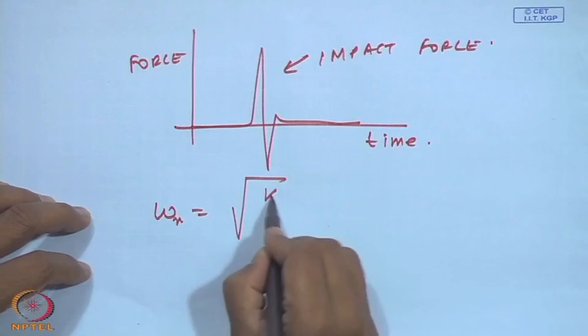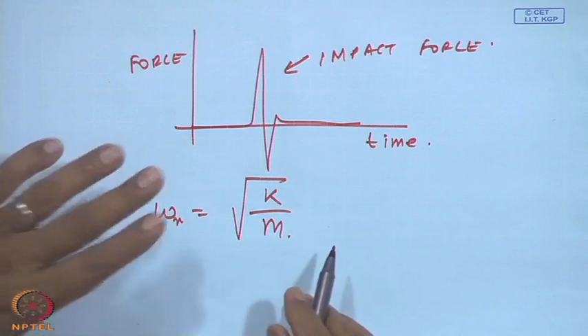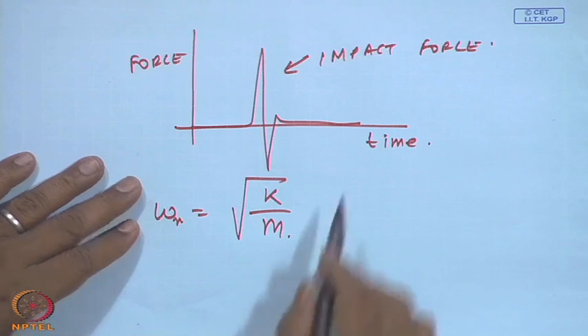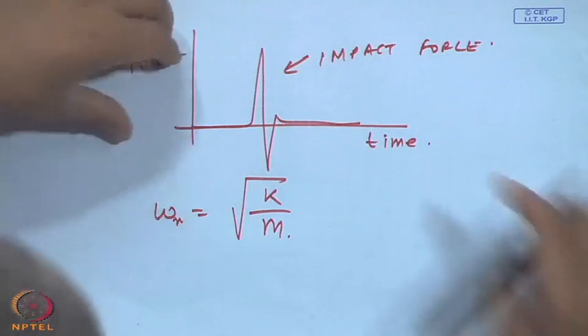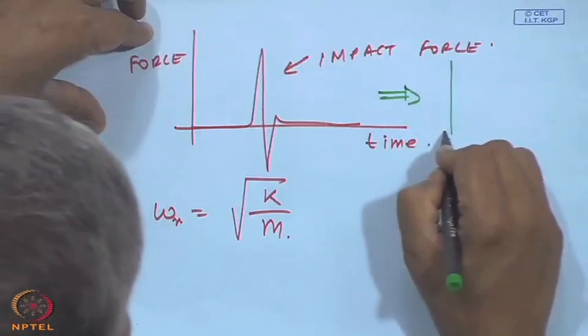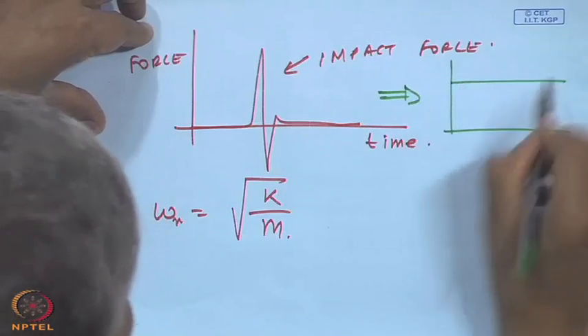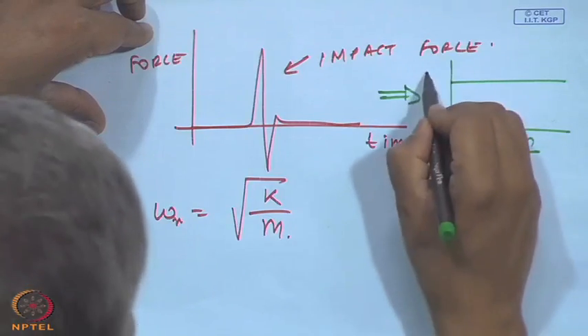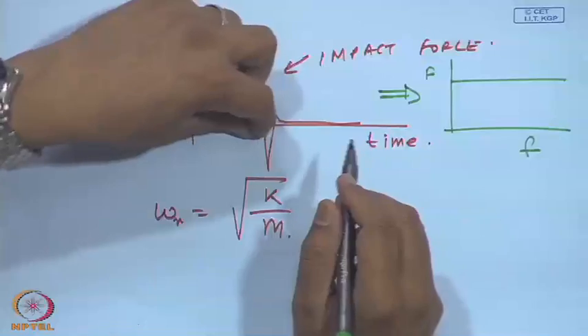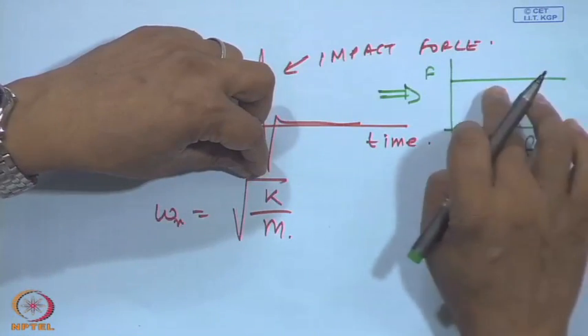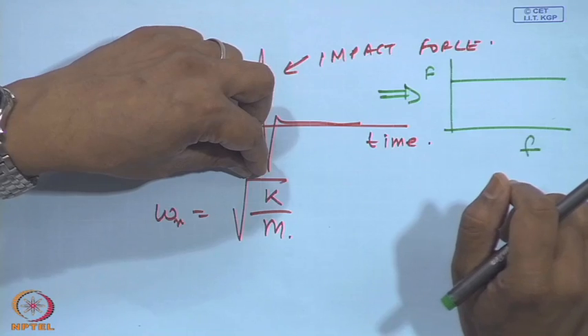So, these impacts, basically these forces, impact the bearing's elastic structure. The bearing has mass, the bearing has elasticity. So, the bearing also has a natural frequency of its own, root of k by m. It has mass, it has stiffness, so it has a natural frequency. Now, if you look at the frequency response of an impact force, it is basically a random force. In the frequency domain, an impact would look like this: a short time impulse force would have a lot of frequencies, a white noise.